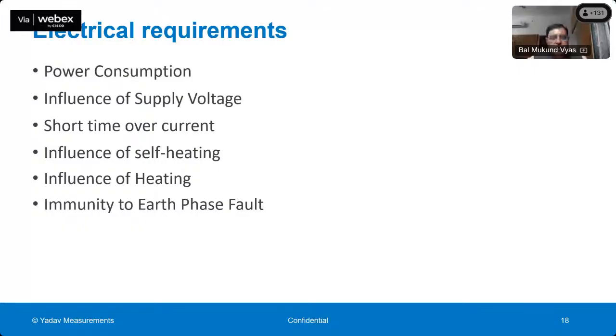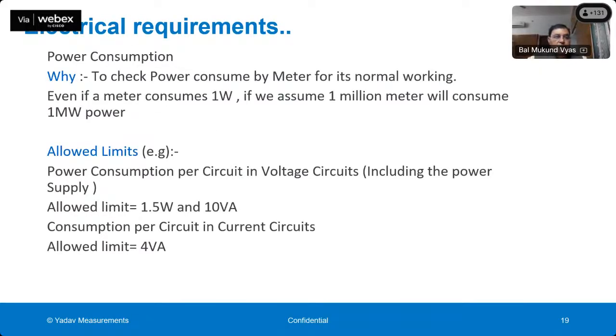Another requirement, as I explained, is about electrical requirements. Within electrical requirements, the meter has to be tested for power consumption, the influence of supply voltage, short time overcurrent, influence of self-heating, heating, and earth fault. Power consumption: because the meter is an electronic circuit, it itself also consumes power. Suppose, as Ashutosh sir told in the starting, we have 40 crore meters, and if each meter is consuming 1 watt, you can imagine how much power can be consumed by the meters throughout the country. So there is a limit in the standard on how much power the meter can consume.